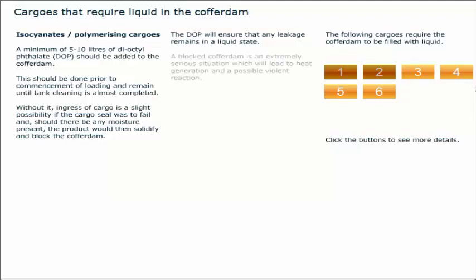A blocked cofferdam is an extremely serious situation, which will lead to heat generation and a possible violent reaction. Indeed, a Framo deepwell pump with a blocked cofferdam must not be run.